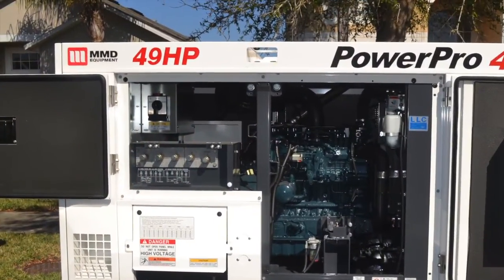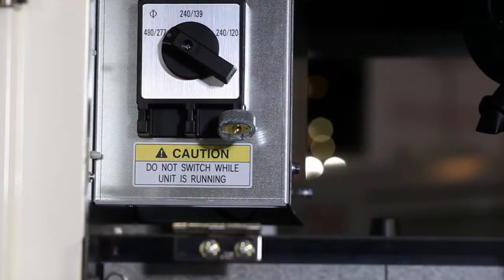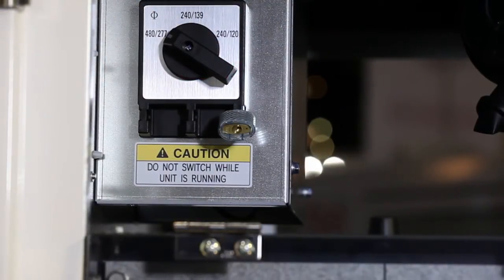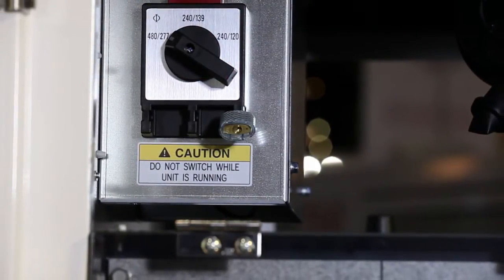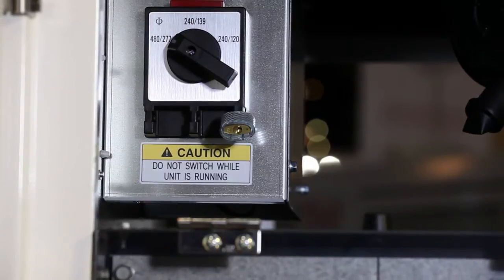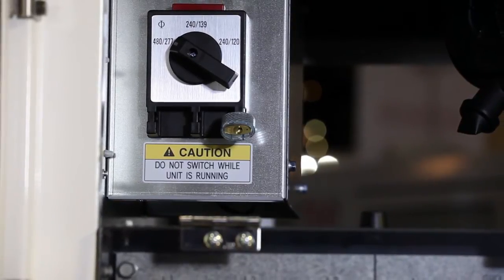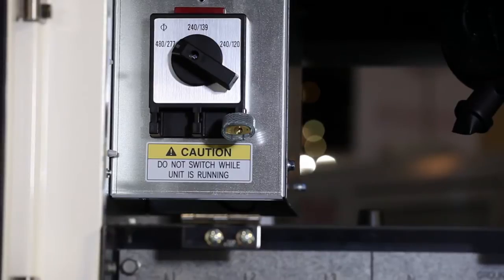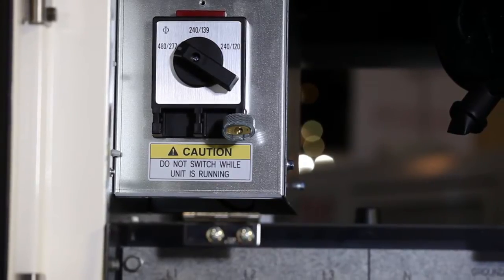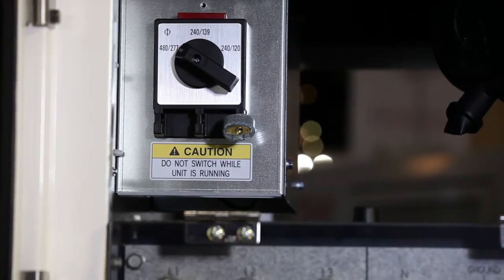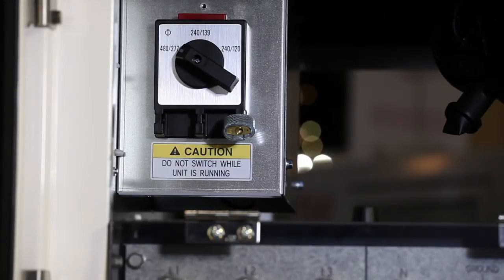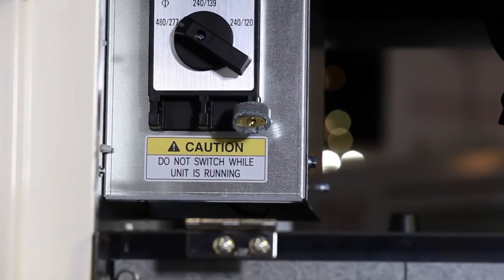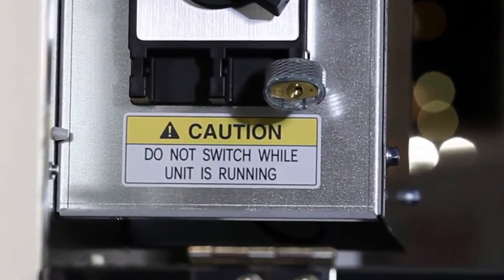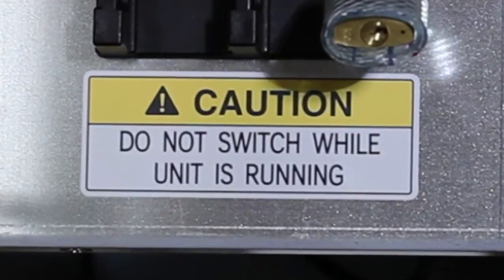Moving to the right side of the generator, we have the main voltage selector switch. Three positions are available: 277/480 volt, 139/240 volt, and 120/240 volt single phase. This switch is lockable to prevent accidental changing of the operating voltage. Please note the caution decal. Do not switch voltage while the unit is running.